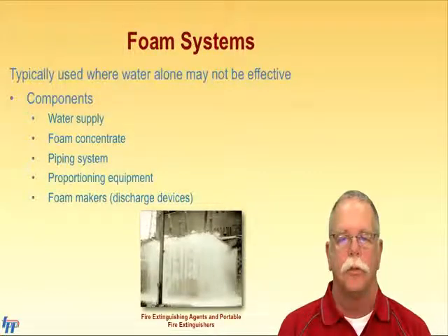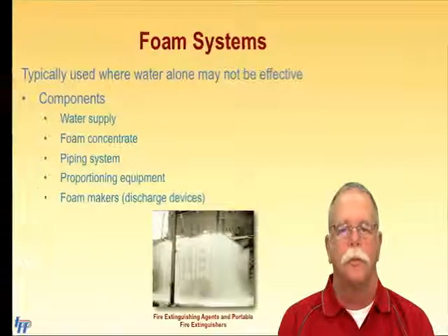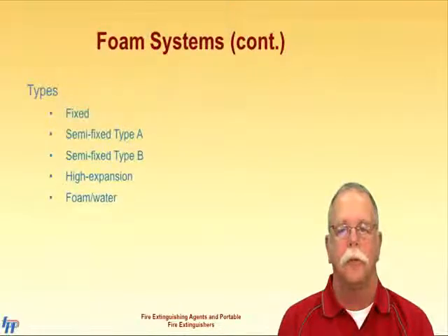Foam systems may be installed to protect areas with flammable liquids processing or storage, aircraft hangars, rolled paper, or fabric storage facilities. Foam system installation guidelines are provided by several NFPA standards. A fixed foam system is a complete system with foam piped from a proportioner station to the location to be protected. It can be a localized application just for the hazard, or total flooding using low, medium, or high expansion foam.